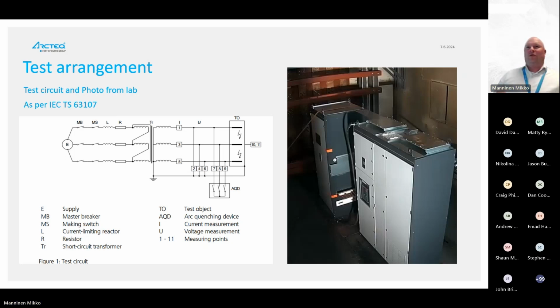On the 28th of April 2020, a new technical specification was launched called 63107, which is the arc flash protection and mitigation system integration standard. There are a lot of IEC standards on how you build low voltage gear, for example 61439, parts 1 and 2. There are standards on how you build the passive protection. We can say passive protection is like mechanical protection. There are testing requirements after TR 61641, which says that the doors should stay closed during the arc flash and after the arc flash. No cotton fabrics 30 centimeters in front of the panel should be ignited, for example.